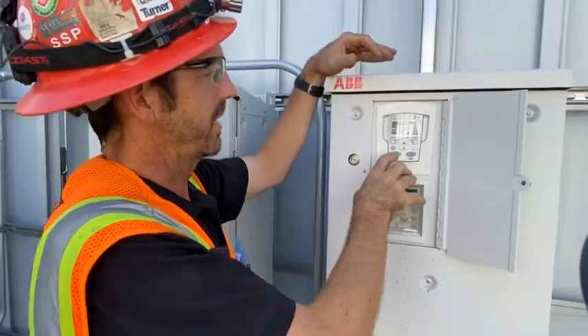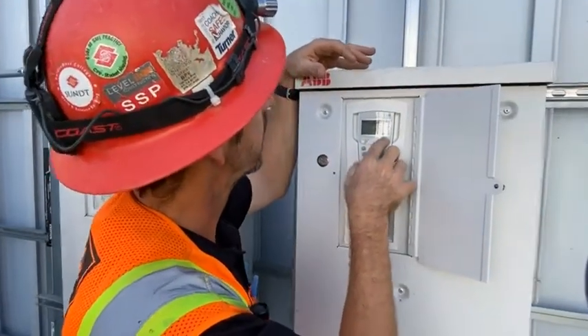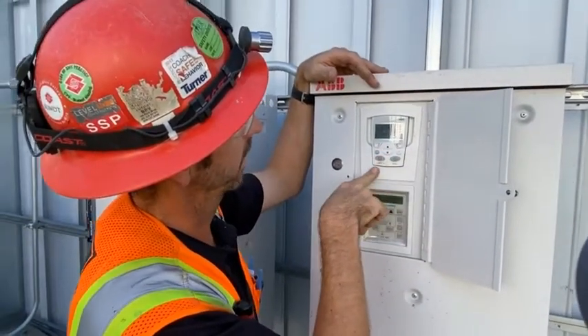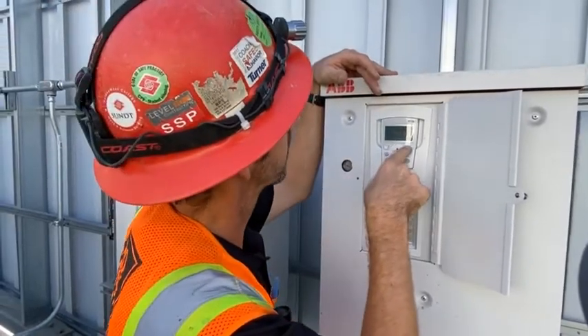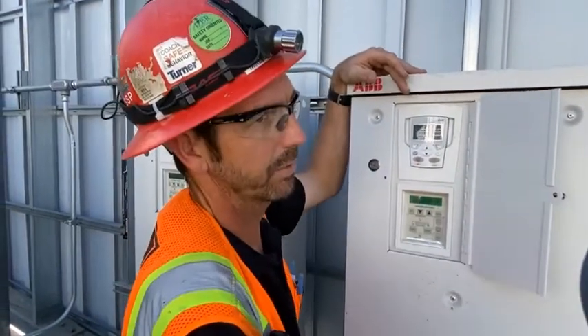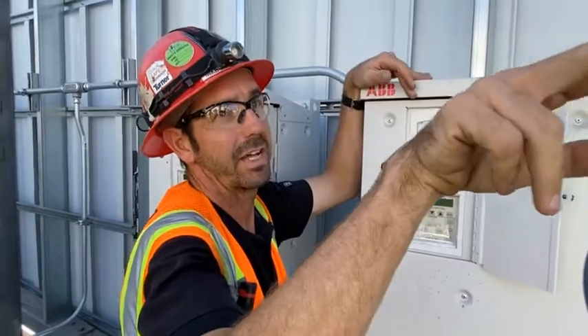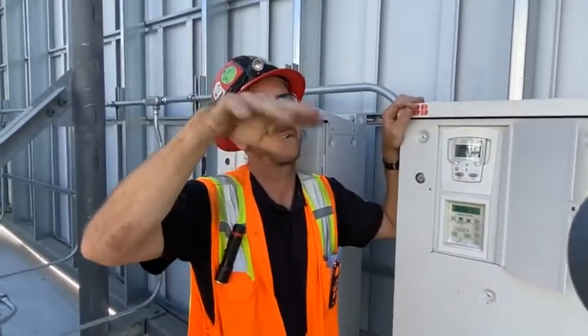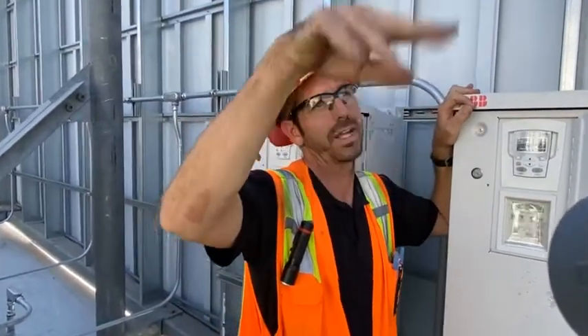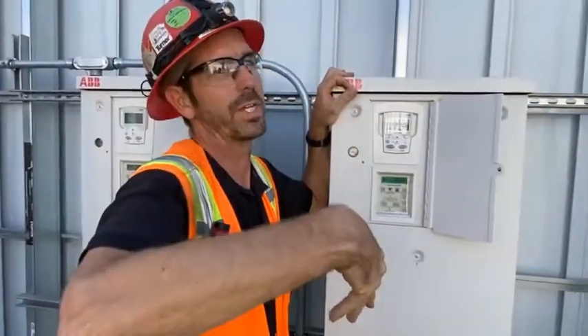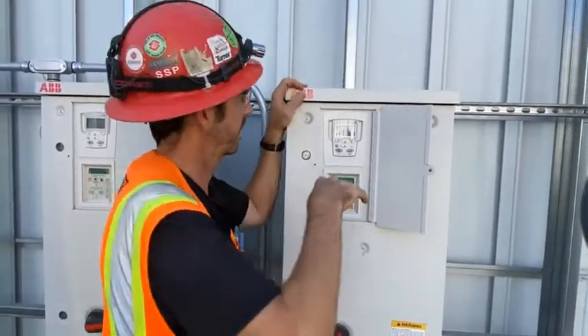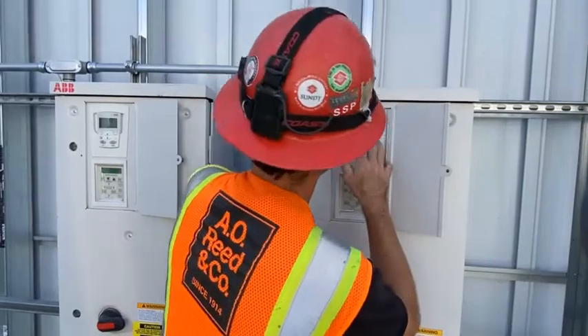So now that we made that change, we need to turn off the unit because we want to save these parameters. I pressed off, it's in ramp down mode. With the style check valves we have, they're gravity check valves. We want to ramp the pump back down. If we just turned it off right away, it would slam the check valve down, okay? So we're ramping it down so it closes the check nice and softly.